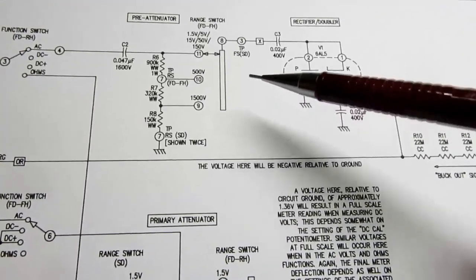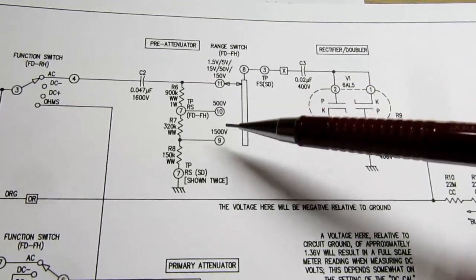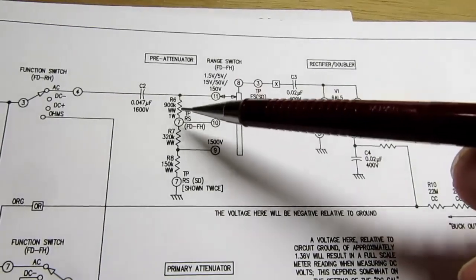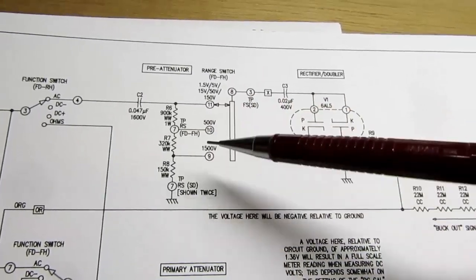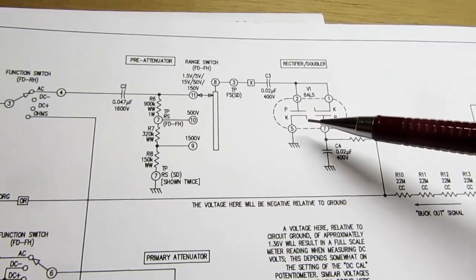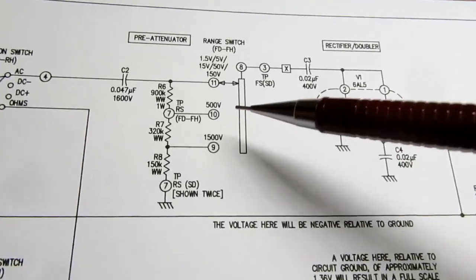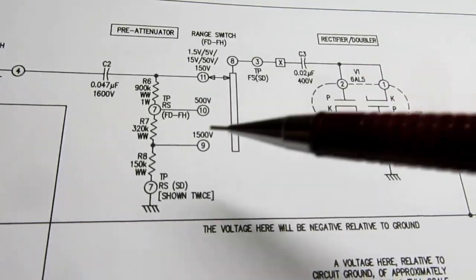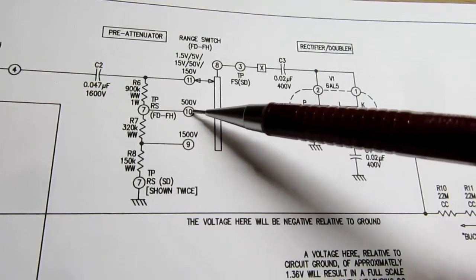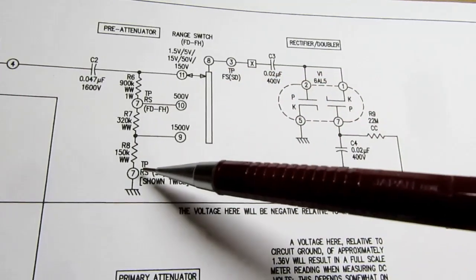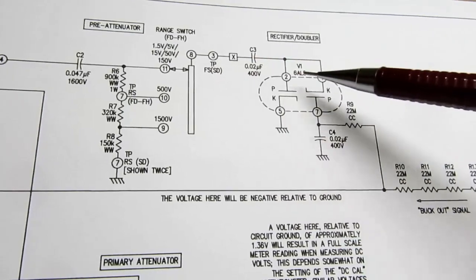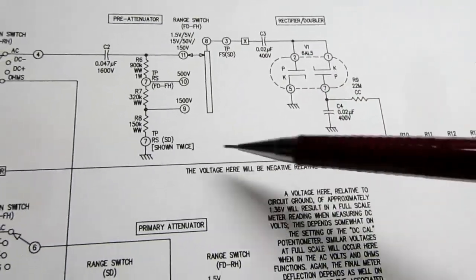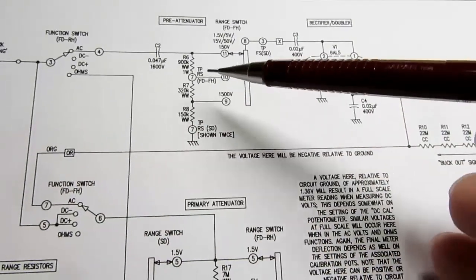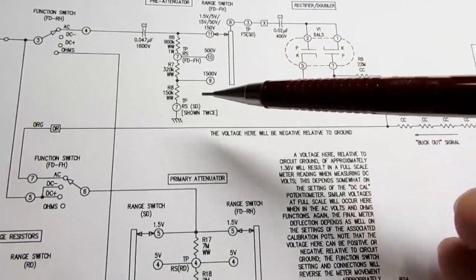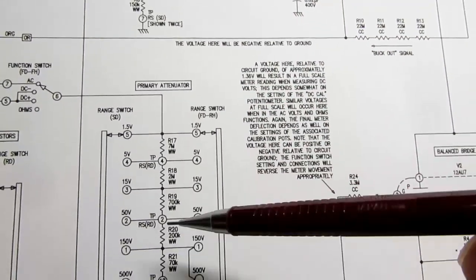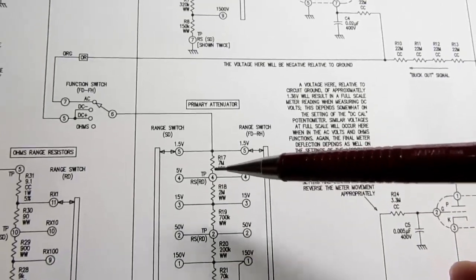So when you do get into these higher ranges, like the 500 volt range or the 1500, you have to divide the voltage down. You have to attenuate it before it's even presented to this rectifier tube. And so that's exactly what it does. If we're in the 500 volt range, we attenuate the signal and then apply it to the rectifier doubler and then go on through, but it's already been attenuated here, so we don't want to attenuate it again here, or at least not by as much.